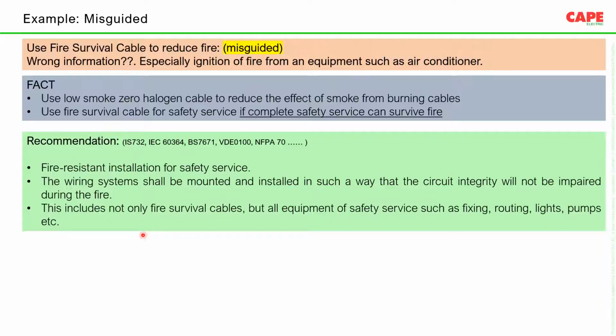So the idea of fire survival is that the entire electrical installation must withstand the fire. So the whole installation shall survive fire. That is the idea. So what is the recommendation? Fire resistant installation for safety service. The wiring system shall be mounted and installed in such a way that the circuit integrity will not be impaired during fire. This includes not only fire survival cable, but all equipment of safety service such as fixing, routing, light, pump, and all the things.